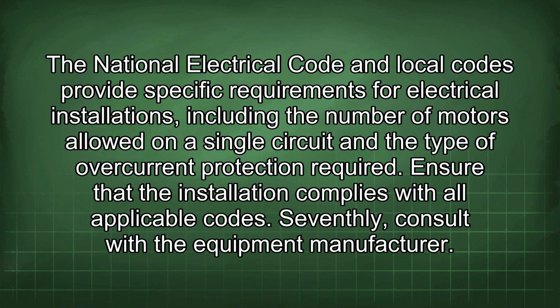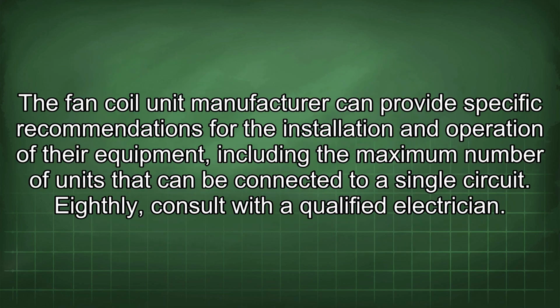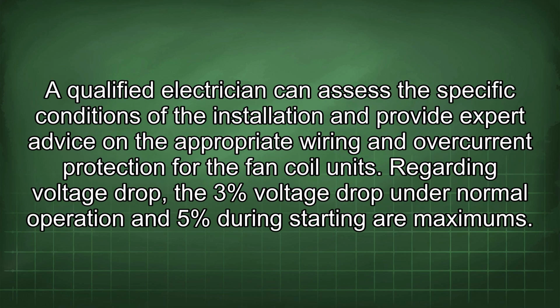Seventhly, consult with the equipment manufacturer. The fan coil unit manufacturer can provide specific recommendations for the installation and operation of their equipment, including the maximum number of units that can be connected to a single circuit. Eighthly, consult with a qualified electrician. A qualified electrician can assess the specific conditions of the installation and provide expert advice on the appropriate wiring and overcurrent protection for the fan coil units.